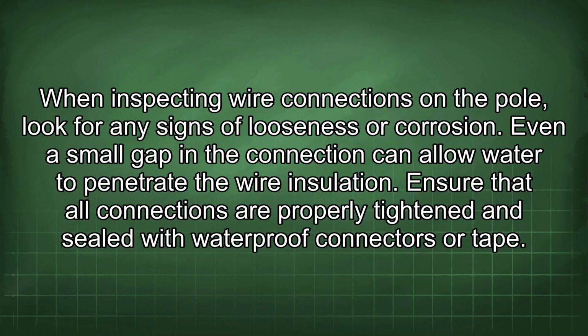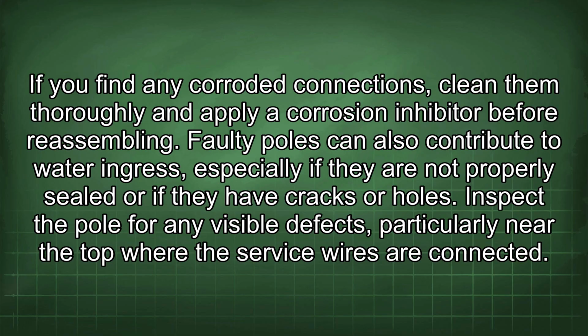When inspecting wire connections on the pole, look for any signs of looseness or corrosion. Even a small gap in the connection can allow water to penetrate the wire insulation. Ensure that all connections are properly tightened and sealed with waterproof connectors or tape. If you find any corroded connections, clean them thoroughly and apply a corrosion inhibitor before reassembling.